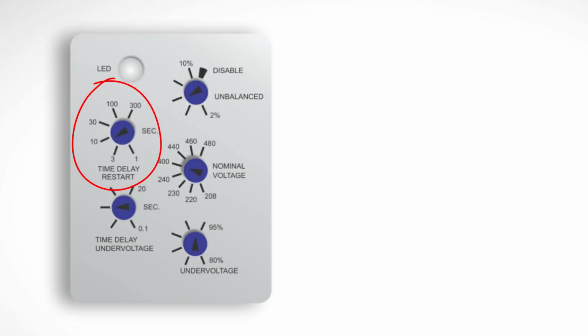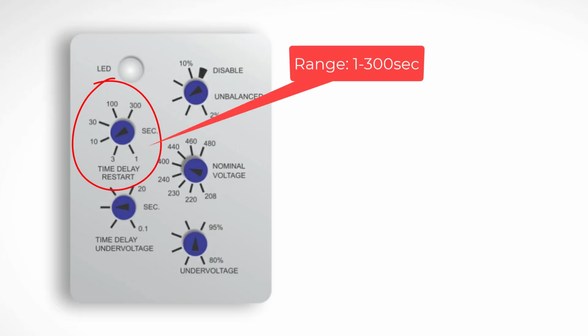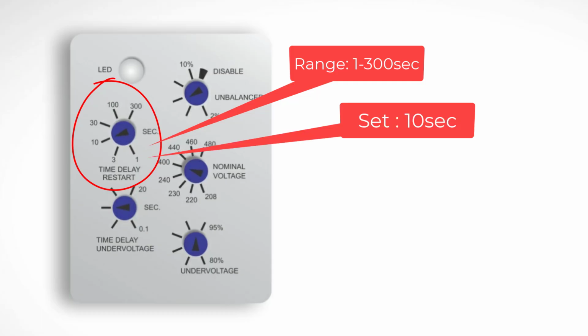This is the restart delay timer. Range 1 to 300 seconds. After a fault is cleared, this delay ensures system stability and no rapid on-off cycling. Example. Let's say you set this timer to 10 seconds. What really happens?